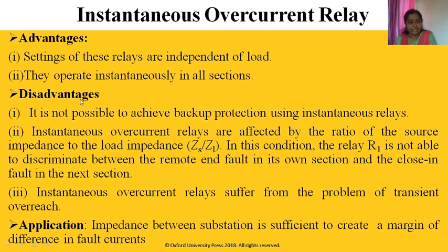Now, what are the advantages and disadvantages? The advantages: they operate instantaneously in all sections, and the setting of this relay is independent of load. What is the disadvantage? As this relay operates instantaneously, it is not possible to achieve backup protection.